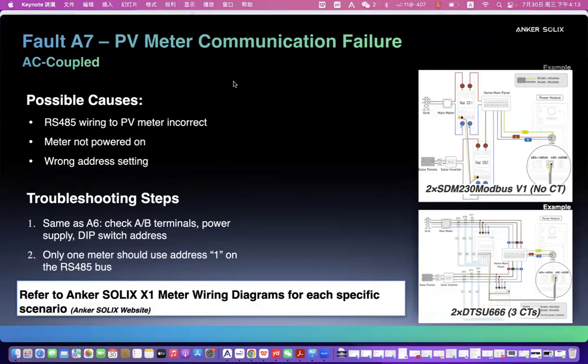PV meter communication failure happens in the AC couple scenario. Not only does it happen to our AC couple inverter, it also happens to our hybrid when the hybrid is used as AC couple. It must have a PV meter. So in this scenario, we need 2 meters, one for the grid and one for solar. I have already mentioned the A6 happens to the grid side meter, but for the PV side, sorry, this is the PV side meter.